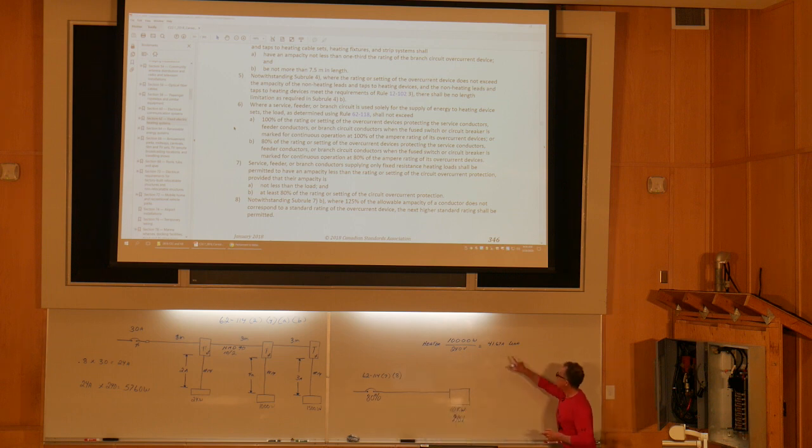So if I take this 41.67 and I multiply it by 1.25, that's going to take me to the minimum ampacity of the circuit breaker. Right?